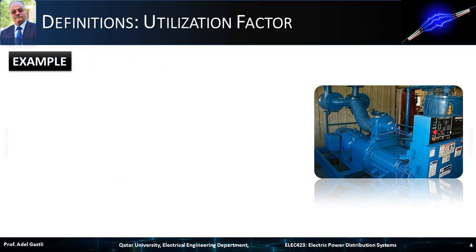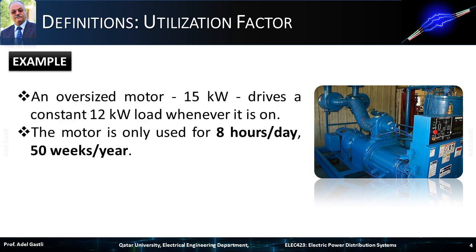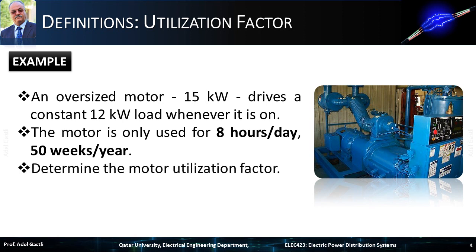Let's see an example of utilization factor calculation. An oversized motor of 15 kW drives a constant 12 kW load whenever it is on. The motor load factor is then 12 over 15, which equals 80%. This motor is only used for 8 hours per day and 50 weeks per year. We want to determine the motor utilization or use factor.